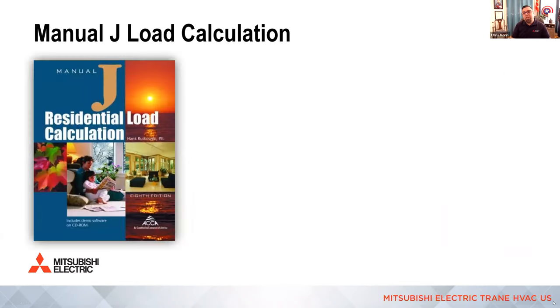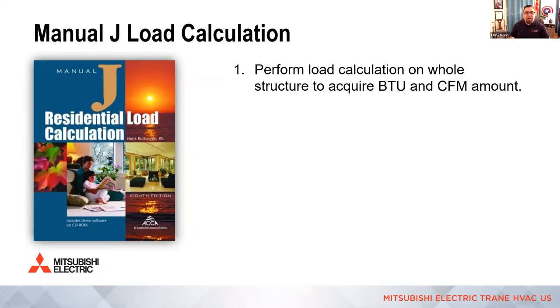So first off, in order to do duct design, you have to follow the design process with HVAC. There's actually more than one manual, right? So Manual J load calculations is without a doubt the first step before you can design ductwork. And typically, you're going to perform a load calc on the entire structure in order to find out how many BTUs you need, right? This is very, very basic. I'm not doing a Manual J class today. I do teach that maybe another day. Obviously, we could spend a whole day on that.